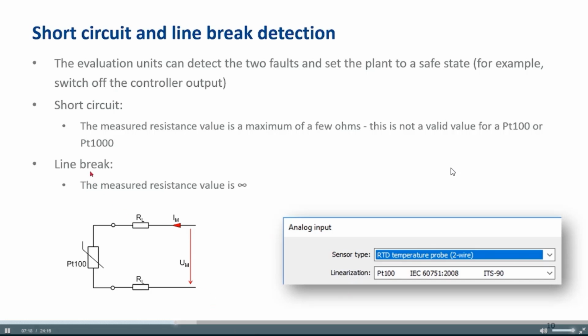If we have a line break, let's say a broken connection wire, then we have an infinite resistance, and the device knows, okay, this is no valid value for PT100, PT1000. The device can recognize that it's not a valid value, and then we switch off the controller output as well. So we can recognize both situations. Now you can say, oh, this is very normal and we can expect this. If you work, for example, with a thermocouple, we will speak about this tomorrow. In this case, you can't detect these both cases. You can't detect this fault. But with a PT100, PT1000, no problem.